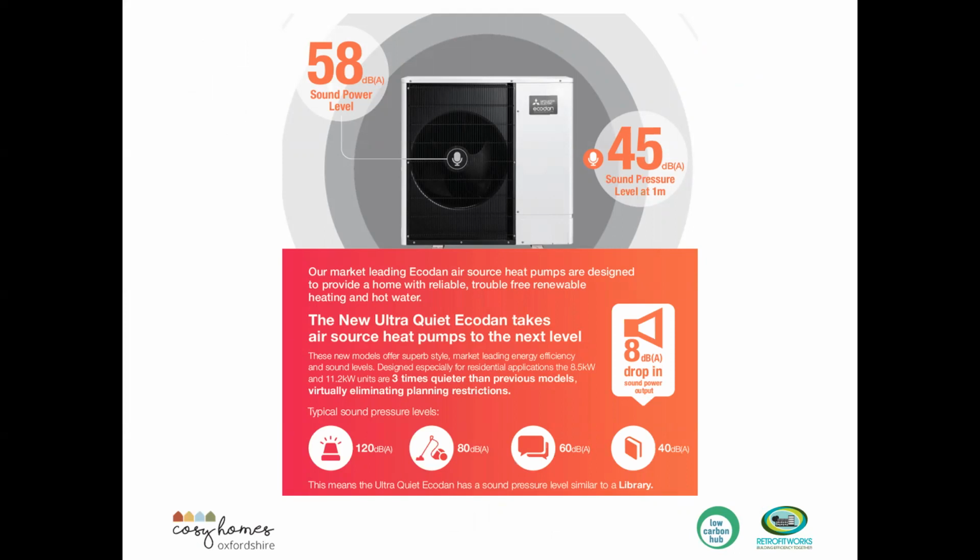A siren is 120 decibels, a hoover is about 80 decibels, me talking now is about 60 decibels, and a library is about 40 decibels. Their heat pump, if you put a microphone on the fan, will be 58 decibels, and if you step 1 meter away, it will be 45 decibels. So on a par with a library, less than talking. With the noise assessment, it's all about line of sight to your neighbour's habitable room or bedroom, and taking a step 1 meter back from that. MCS, the Microgeneration Certification Scheme body, have a set procedure for monitoring that.